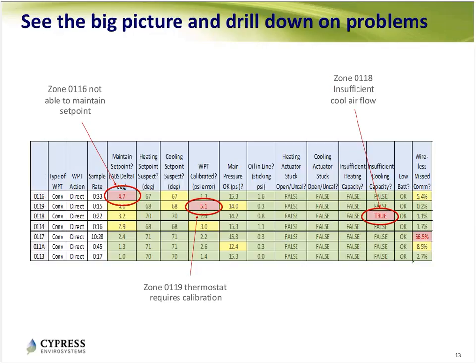At the very top are the zones with the most problems, like those that cannot maintain set point. For example, this one with 4.7, the upper left-hand red one, means it's not controlling temperature well. That zone is on average about 5 degrees off from set point, which is a problem. The yellow ones are off a little less, between 2.5 to 4 degrees. The green ones are pretty comfortable and close to set point.